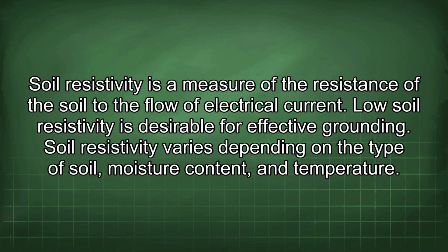Soil resistivity is a measure of the resistance of the soil to the flow of electrical current. Low soil resistivity is desirable for effective grounding. Soil resistivity varies depending on the type of soil, moisture content, and temperature.